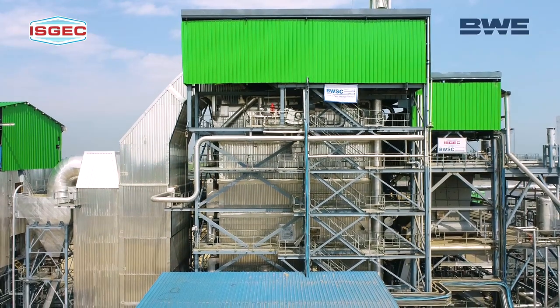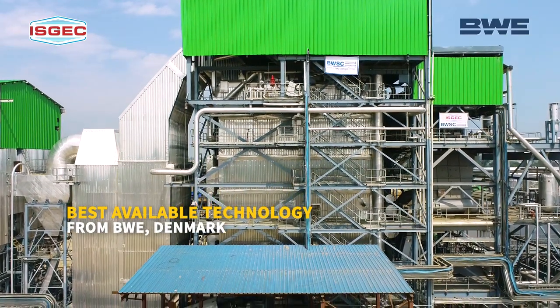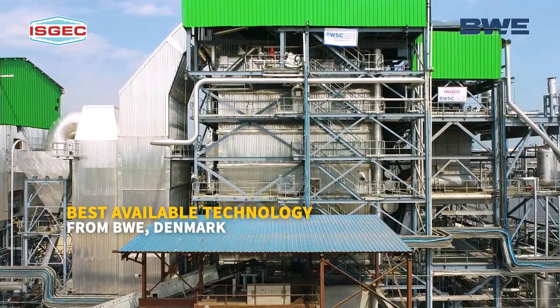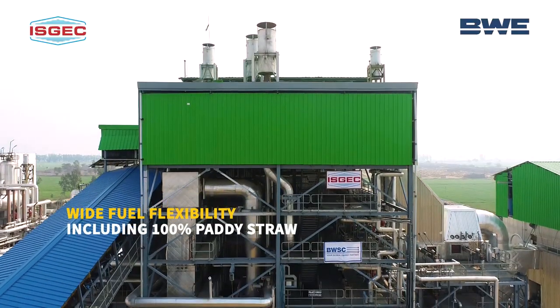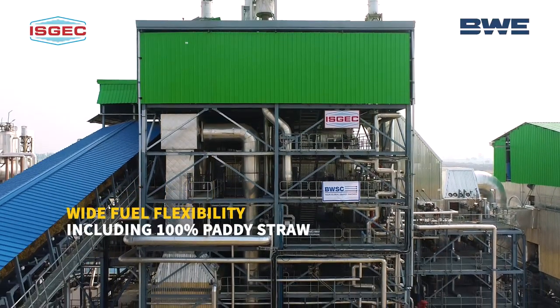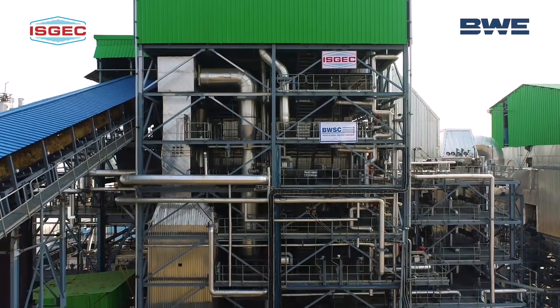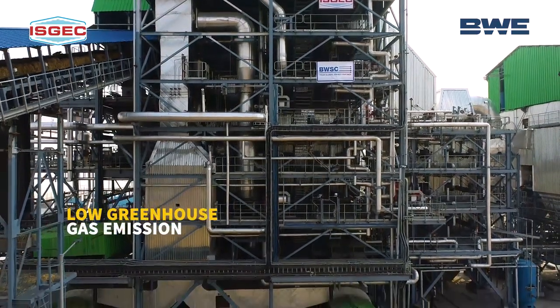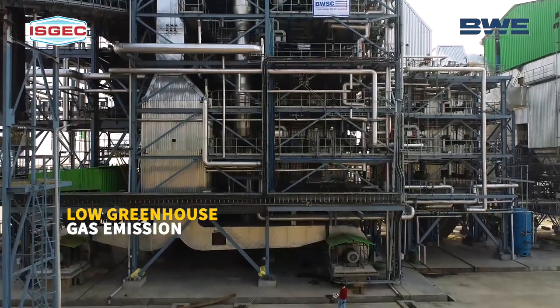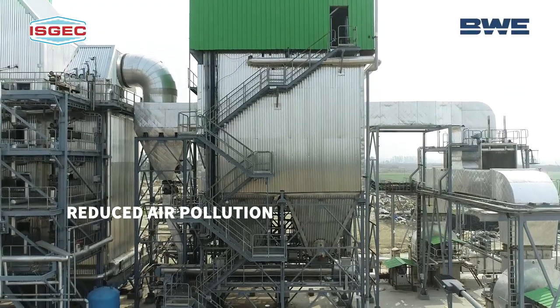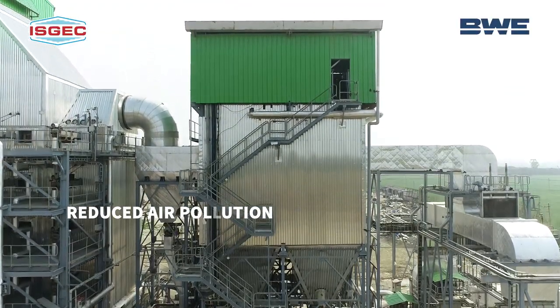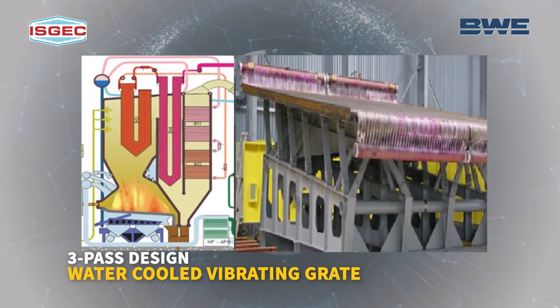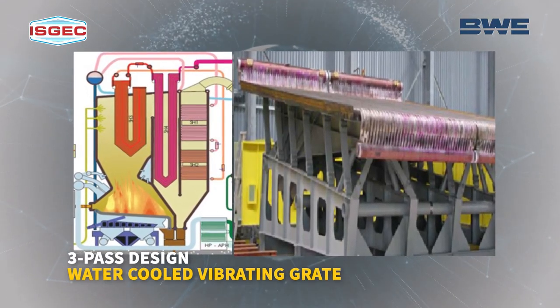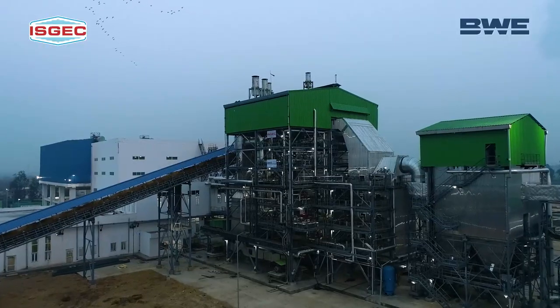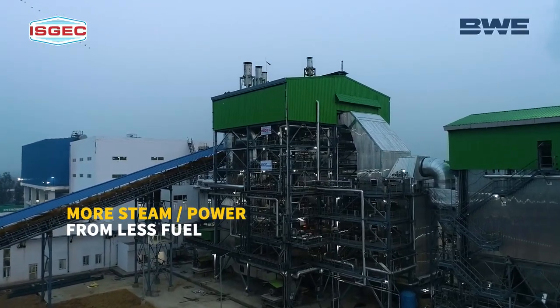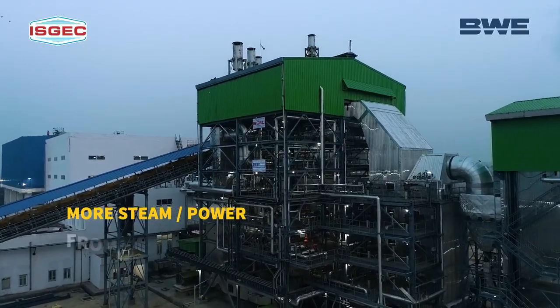The boilers are built on the best available technology from BWE Denmark and offer wide fuel flexibility, including 100% paddy straw, low maintenance and operating cost, and ensure low greenhouse gas emission. The main constructional features with added advantages are a three-pass design water-cooled vibrating grate, providing the best thermal efficiency by generating more steam from less fuel.